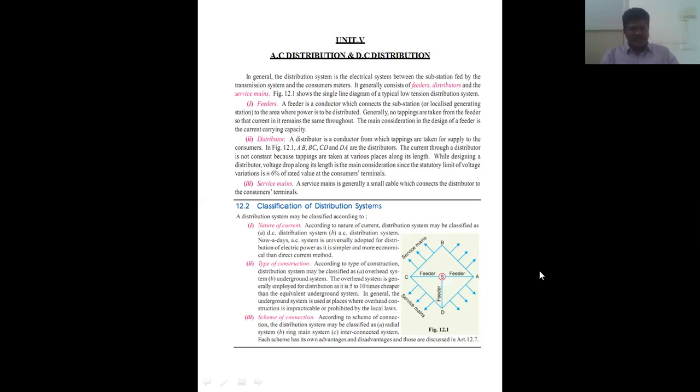The distributor is the conductor from which tappings are taken for supply to the consumers. The current through the distributor is not constant because tappings vary along its length. While designing the distributor, voltage drop along the length is the main consideration, with the permissible voltage variation being plus or minus 6% of rated value at consumer terminals.